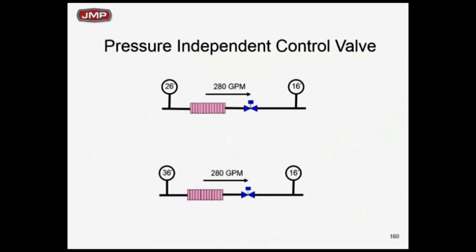What happens if I put a pressure-independent control valve into the same situation? Now I changed the valve to a pressure-independent control valve. I got 10 feet of drop, 26 in, 16 out, 10 feet, 280 GPM. Great. What happens to a pressure-independent control valve if I double the pressure drop across it? If I go from 36 feet to 16 feet, what happens to my flow? I'm not changing the position of the valve now. A pressure-independent control valve with the spring load will pick up on that differential pressure increase instantaneously and hold it to 280. So now I have the ability, with a constant change in differential pressure, to hold my delta T.